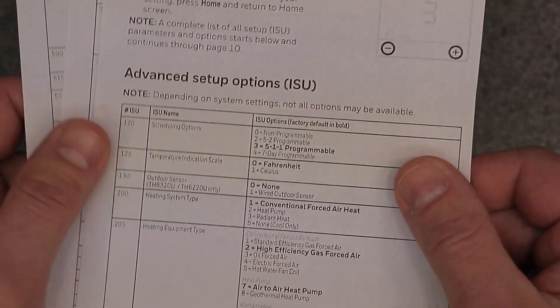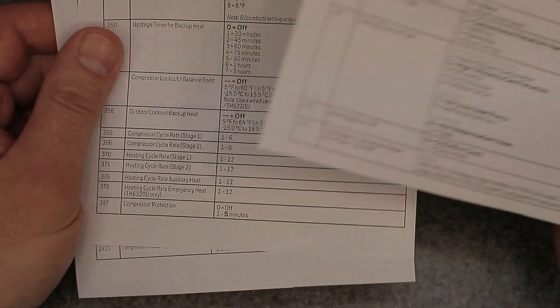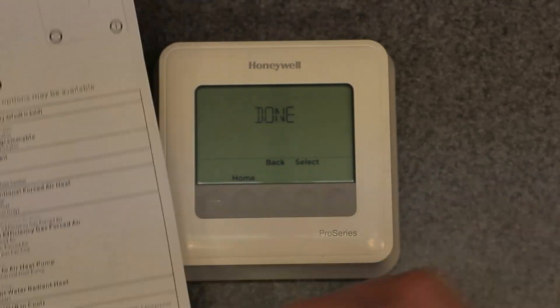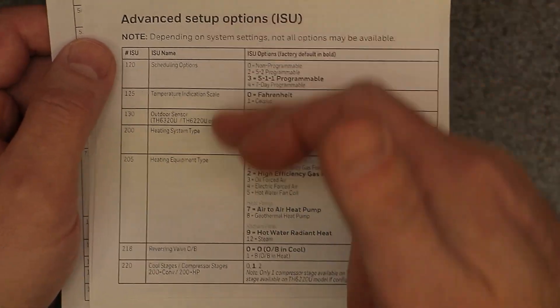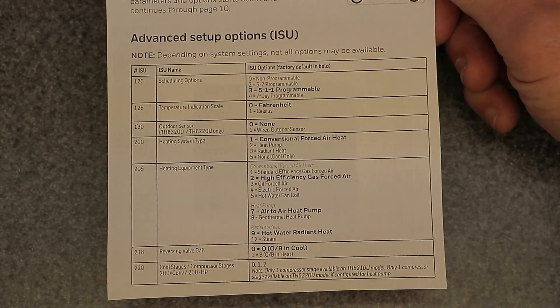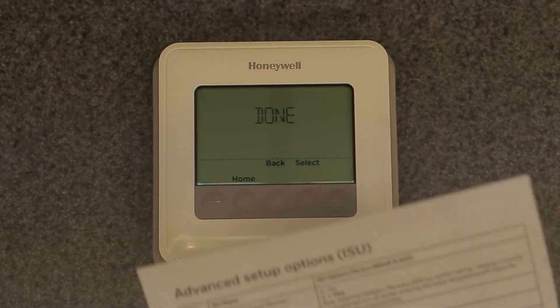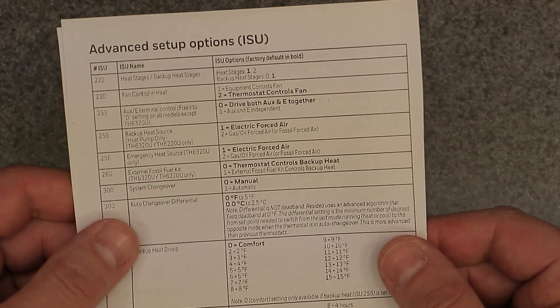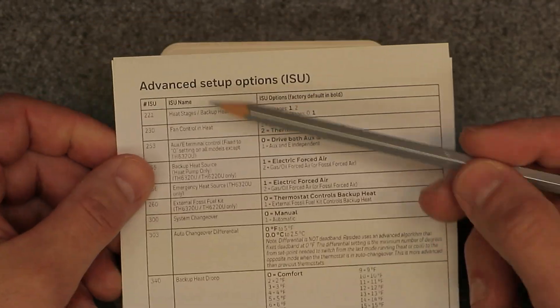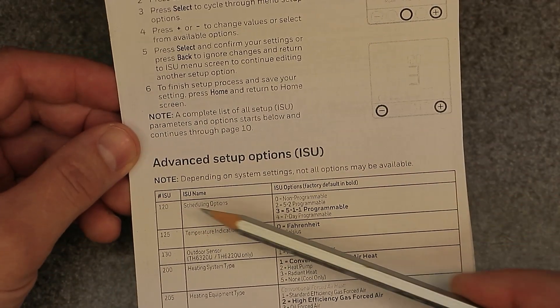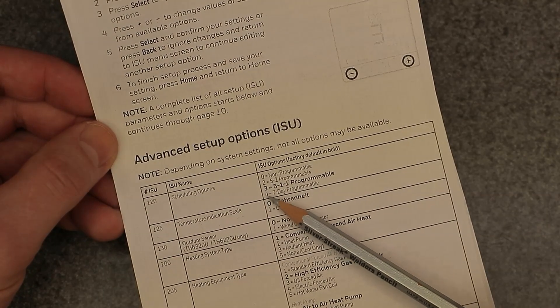This list is extremely hard to find — I had to search extensively. It actually comes from the T6 Pro manual, but it covers the T4 as well. I'll post a link to this information below the video. I'll go through a quick snapshot of each function, number, and setting. The first one is 120: scheduling options, with values 0, 2, 3, or 4. Next is 125: temperature indication scale, 0 or 1 for Fahrenheit or Celsius. Then 130: outdoor sensor, 0 or 1.